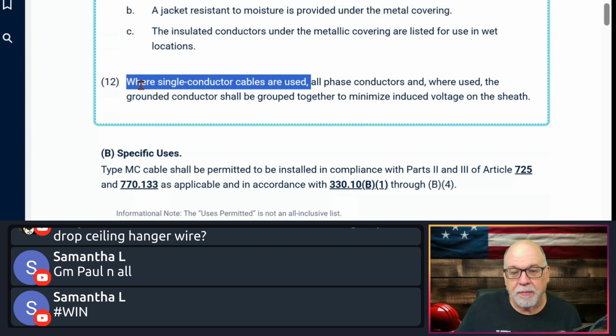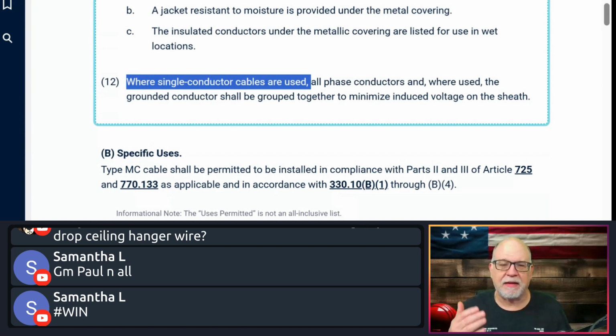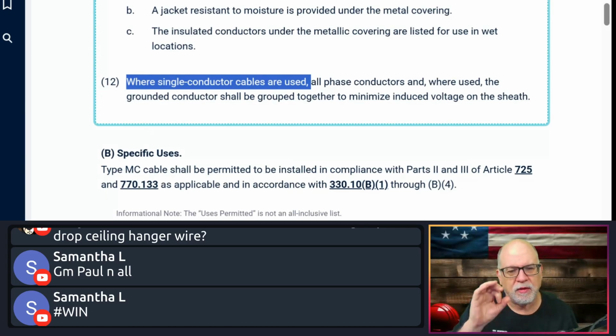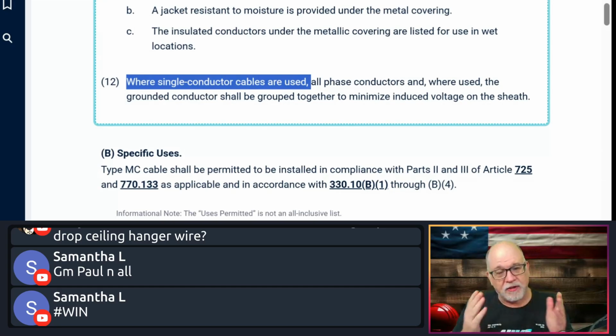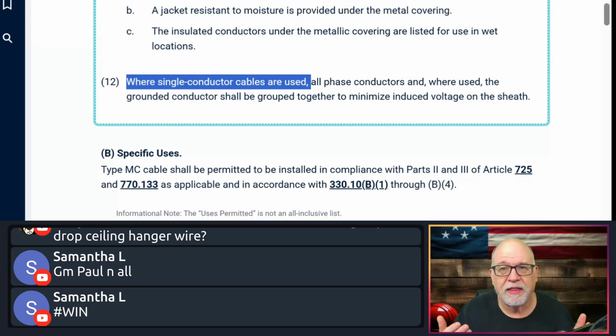There's MC cable that's made out there, for example, in the 2196 fire type, the two-hour rating. They will actually make an MC with a single conductor in there, and it gets wired very similar to how you would do an MI cable, in very close proximity. It's very unique in how you'd run it. But they do make a single conductor MC out there.